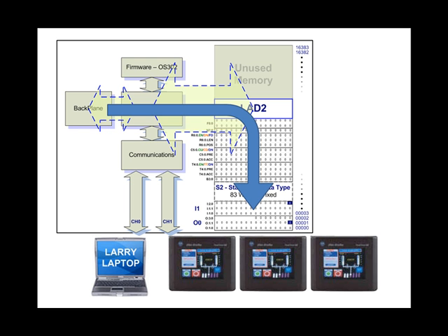How long this takes is dependent solely upon the quantity of words that have to be activated one at a time onto the backplane and transferred into memory locations. Remember, some of the processors in this family allow 30 possible slots of I/O, that's slot 1 through slot 30, and each slot is capable of transacting 32 words in and 32 words out.